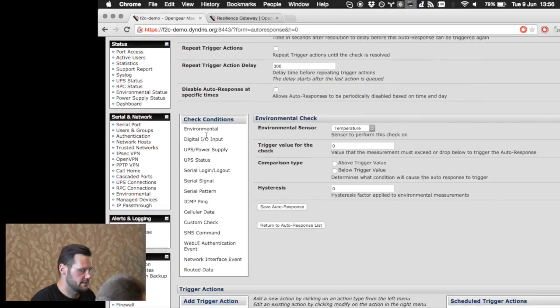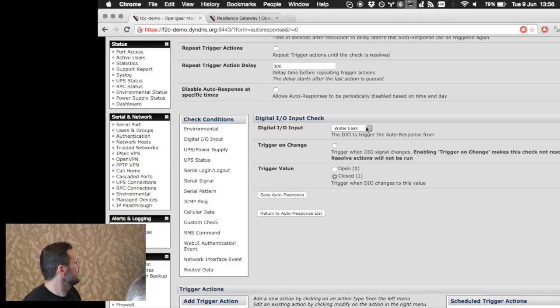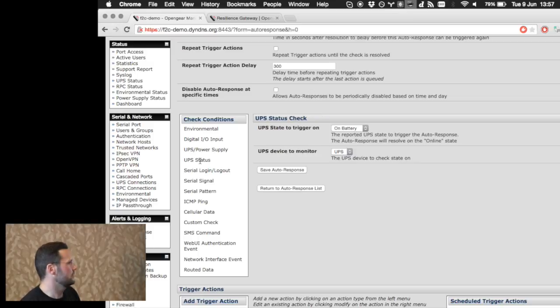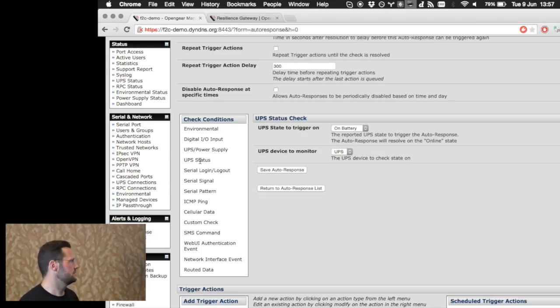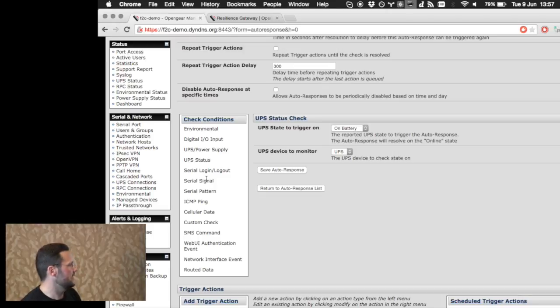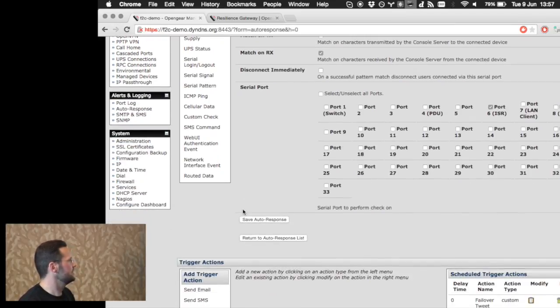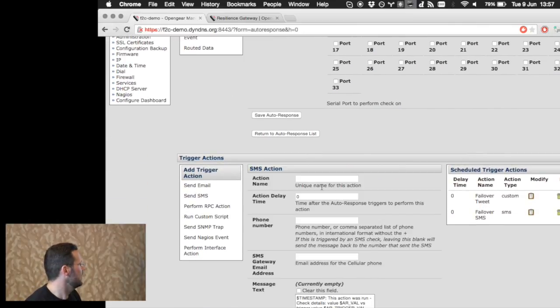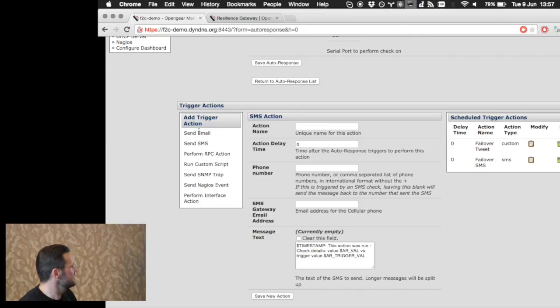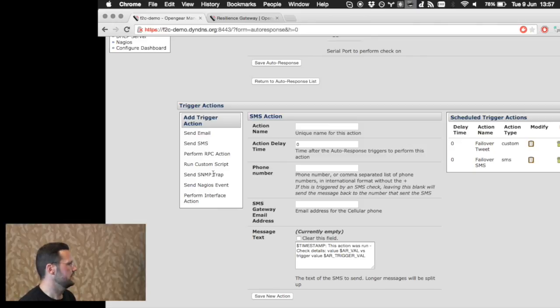In an autoresponse you've got a whole bunch of different check conditions. It could be environmental, a digital IO — we've got built-in open/close sensors that could be hooked up to a water leak detector or smoke alarm. We also support over a hundred different vendor UPS systems over USB — so we can protect when it goes from online power to battery power and send alarms or do load shedding. The one I was using for the demo was a serial pattern match — it could be a regular expression or a simple string to match on. When I see 'reachability up to down' on my ISR console, it takes an automated action — in this case a built-in send-SMS alarm. You can also send an email to a trouble ticketing system to raise a ticket.